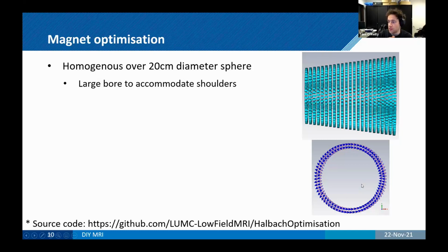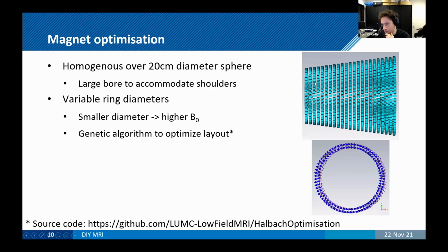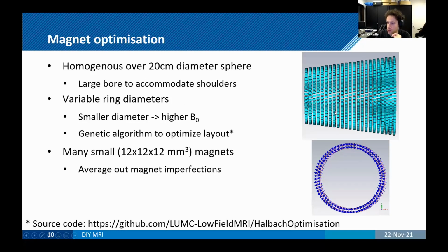So you need to optimize your magnet in order to prevent that field from dropping off. And the way that we decided to do this was by allowing the ring diameters of your magnet to vary along the length of the system. So smaller ring diameters are associated with a higher magnetic field strength. And if you place those on the edges of your magnet, where you're seeing the magnetic field lines drop off, you're able to elevate the magnetic field there, and that's preventing the field from dropping off. In that way, you really get a much more homogeneous system.